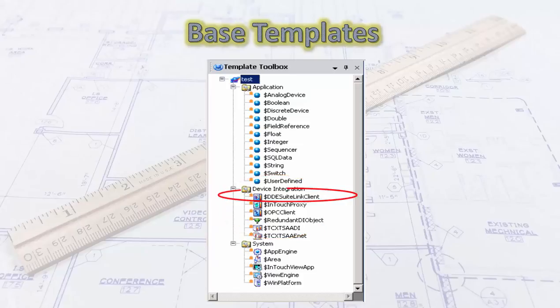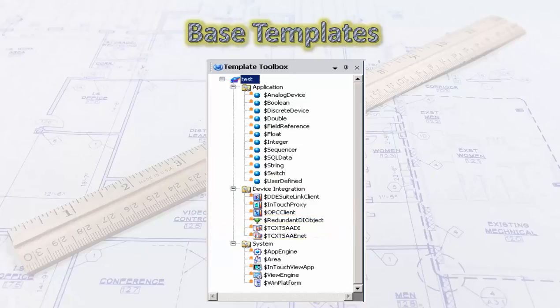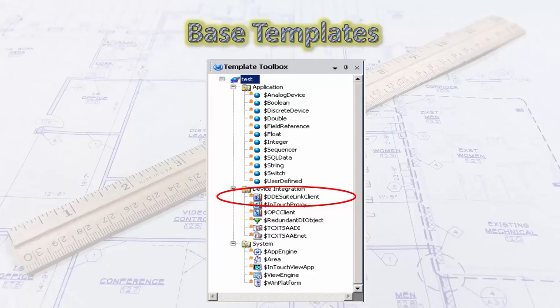Device integration templates include DDE SuiteLink, InTouch Proxy, OPC Client, and Redundant DI. Those two bottom ones are device integration objects specific to DAS servers deployed inside the galaxy. DDE — dynamic data exchange — is a protocol that's been around for a long time and is no longer supported by Microsoft. Built into that client is also the SuiteLink client, which is Wonderware's native communication protocol. We use the SuiteLink client to communicate with DAS servers that Wonderware has provided for communicating with Allen-Bradley, Modbus, and other devices.